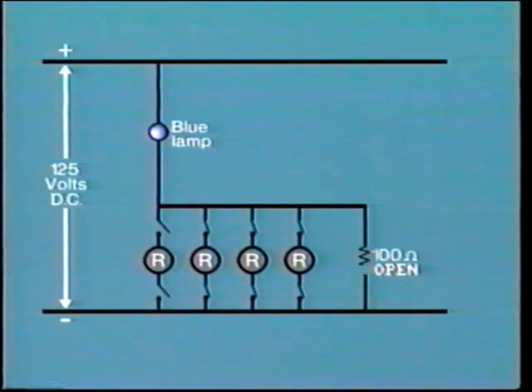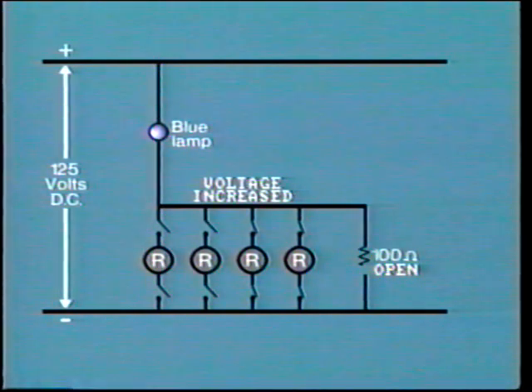Now, as each of the coils were opened, the voltage across the remaining coils increased. Remember, these are in series with the indicating circuit. Eventually, as the 3rd coil was disconnected, the voltage across the remaining coil rose sufficiently to operate the relay and trip the breaker. The 4 auxiliary relays have now been replaced with one multi-contact relay.